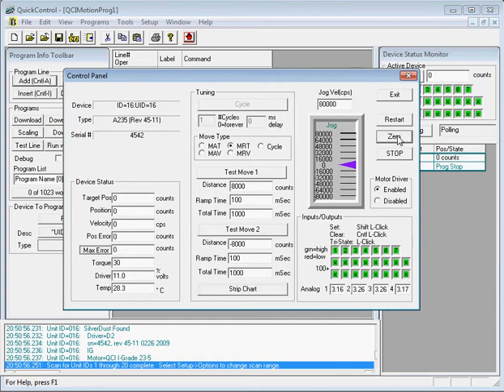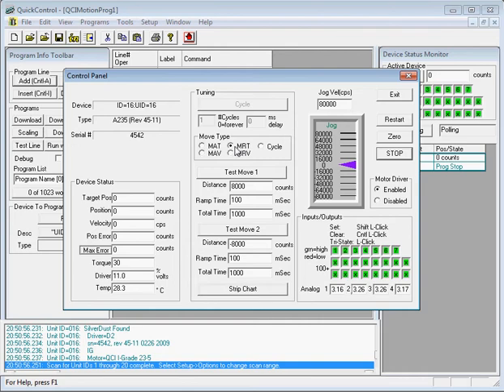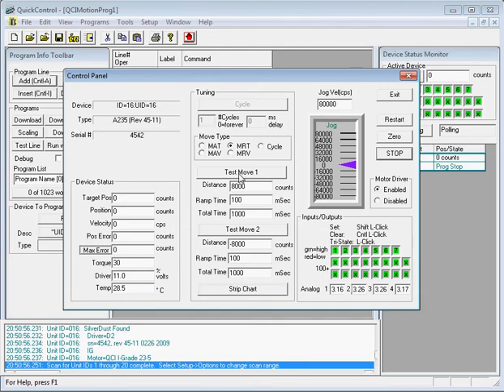We can also test a move command by selecting one of these four move types. I'll go ahead and select the MRT, which is a move relative time-based command. So I'll give it a distance of 8,000 counts, ramp time of 100 milliseconds, and a total time of 1,000 milliseconds. So clicking the Test Move One button will command the motor to move 8,000 counts in one second.